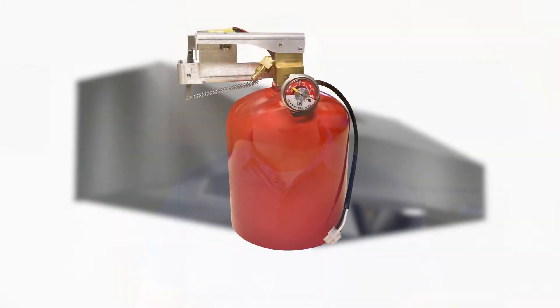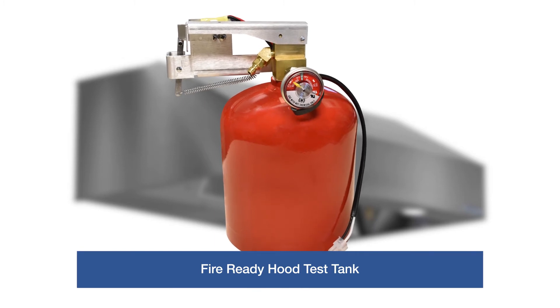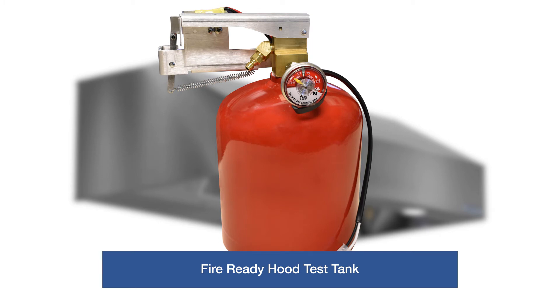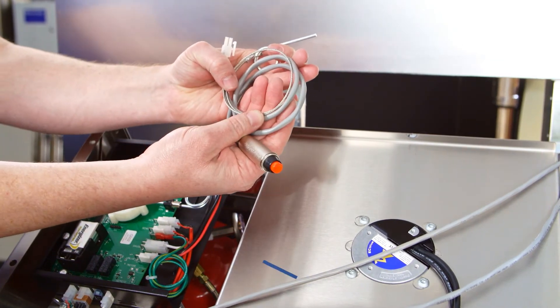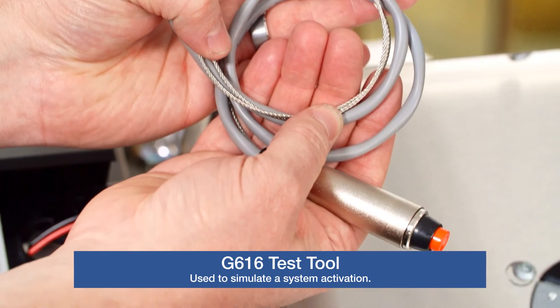If a fire system puff test is required, a test tank like this one can be provided. These tanks are only for test purposes and are charged with nitrogen. The purpose of a puff test is to demonstrate proper fire suppression operation. Authorized guardian distributors and installers should have a G616 test tool that is used to simulate a system activation. Note that a remote pull station option will also serve the same purpose for testing.